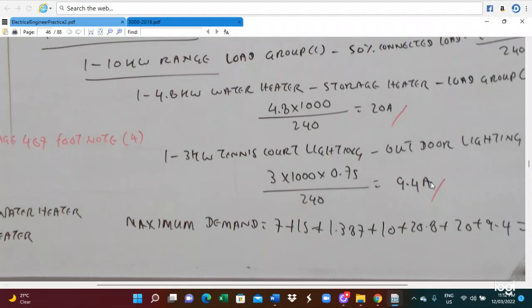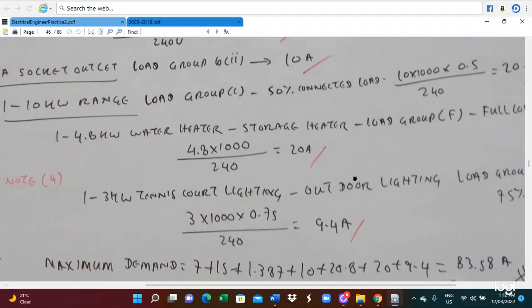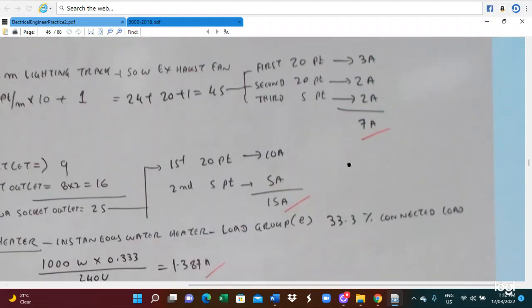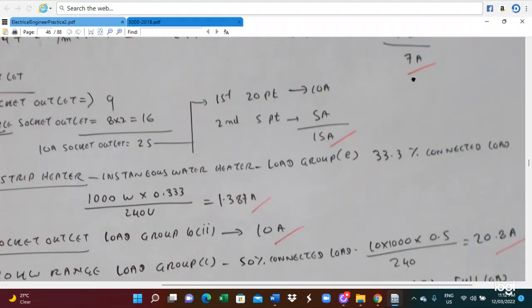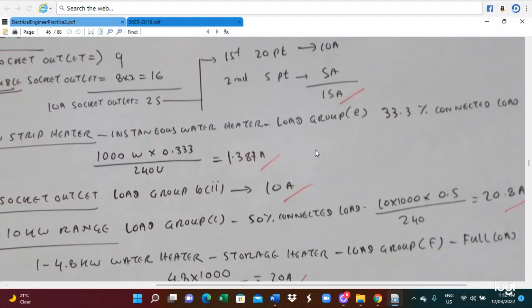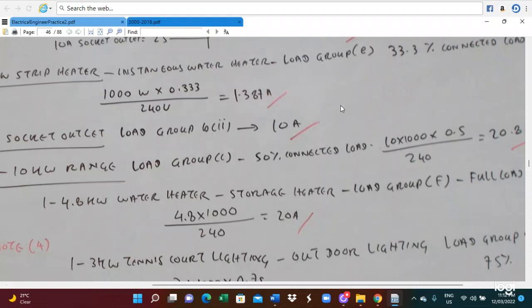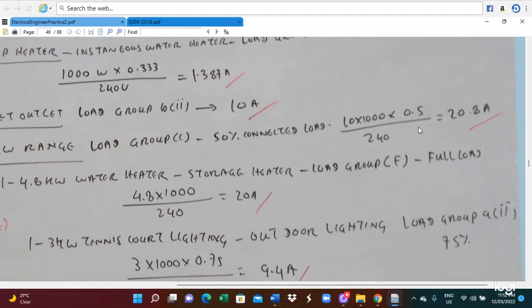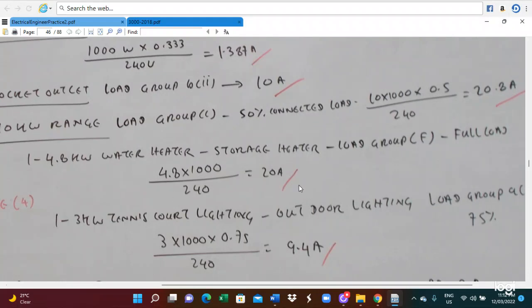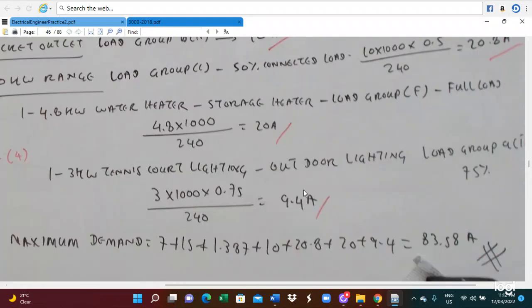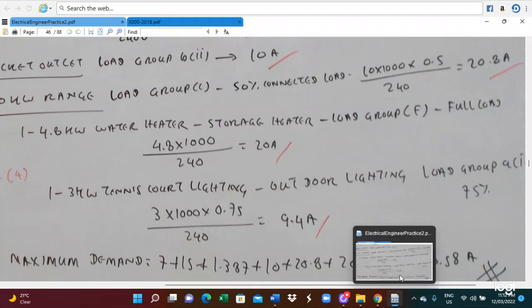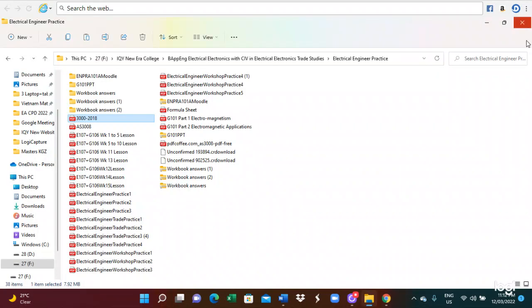So then you have to add everything. From here, all the lighting points are 7 ampere. And also the socket outlets, 10 ampere socket outlet, 15 ampere. Instantaneous water heater, 1.387. 15 ampere socket outlet, 10 ampere. And electric range at 20.8 ampere. And 4.8 kilowatt water heater, 20 ampere. And also tennis court lighting, 9.4. You add everything, you get 83.5. So this is the way we calculate the maximum demand.